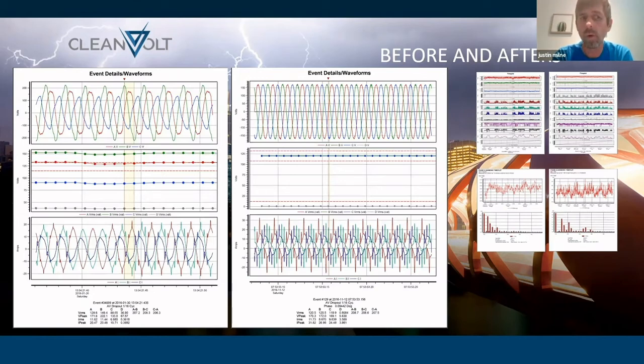We also noticed that there was 30 volts on the neutral. This indicated to us that there was a wiring condition. We did find out that the run that went to their laundry was an underground cable that was buried in 1980, so it was about 25 years old, or 35 years old, sorry, at the time. So there was a good chance that some rock or something had penetrated the sheath and caused this bleed from one of the phases onto the neutral.